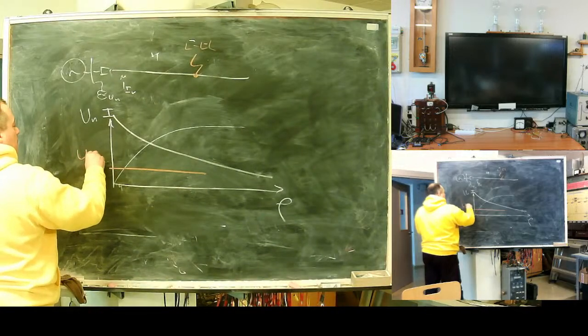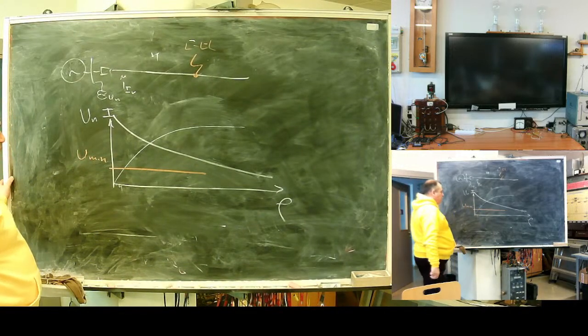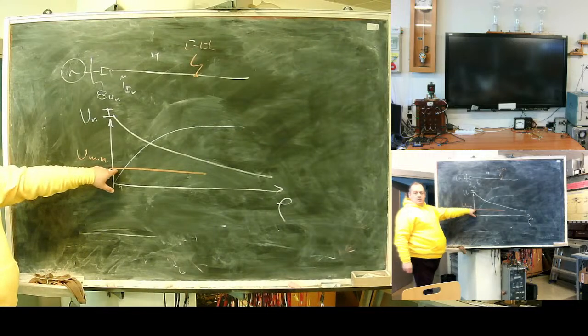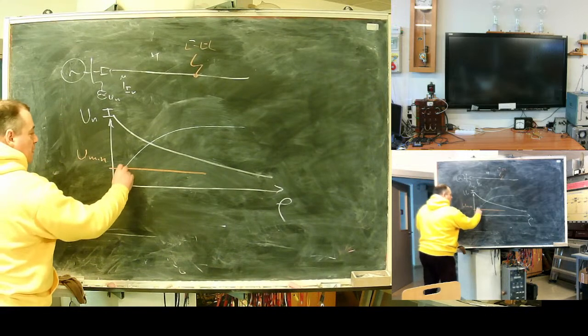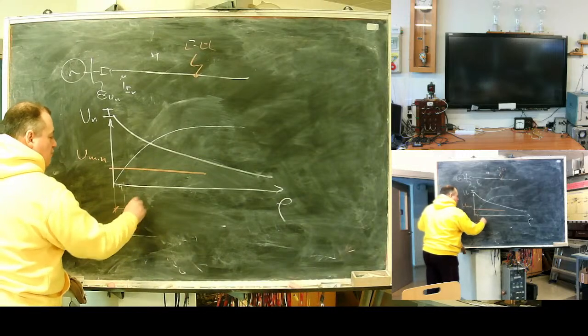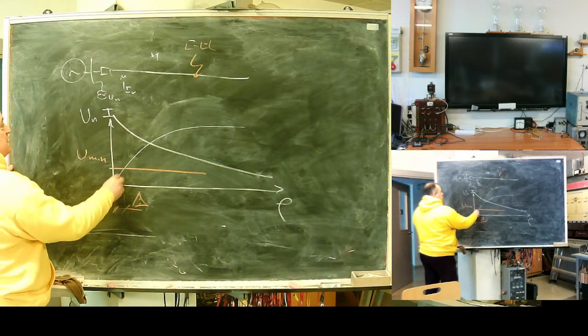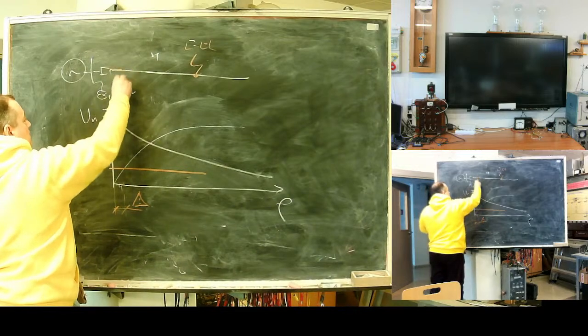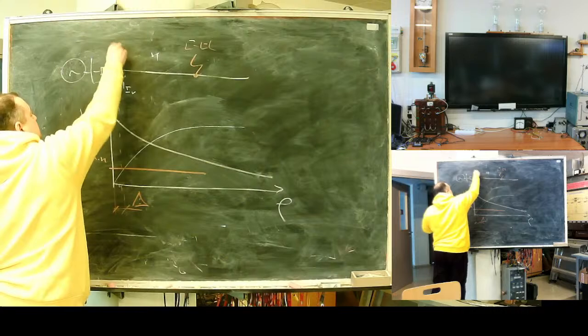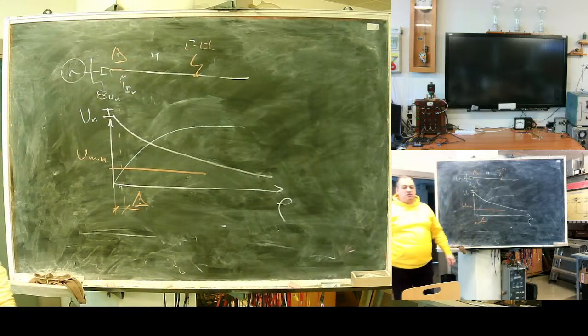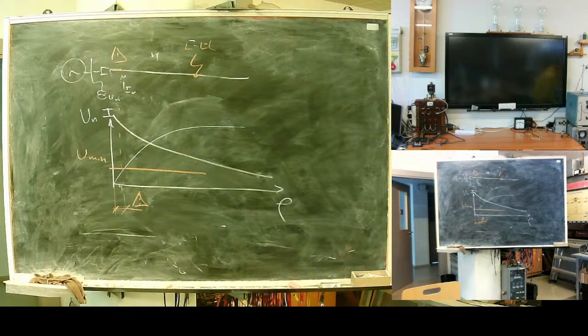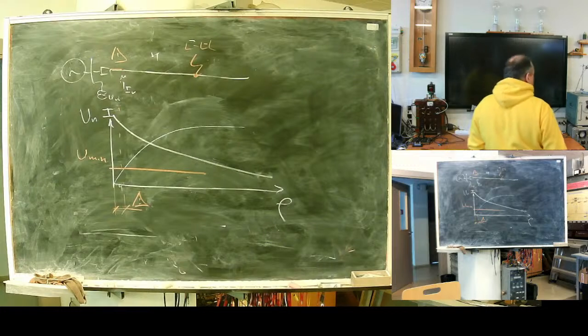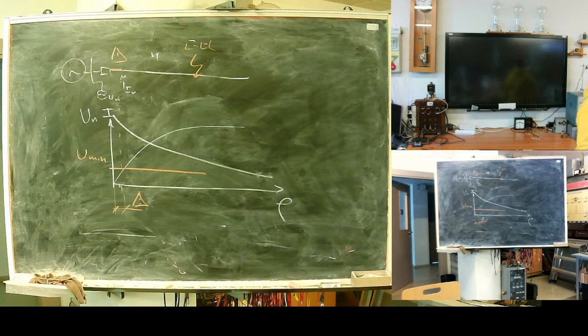Let's say, minimal voltage. What does this mean? Our protection will fail to operate in this area, approximately. This part is the so-called blind zone. In case of three-phase fault, protection will not operate because it is not possible to determine direction.